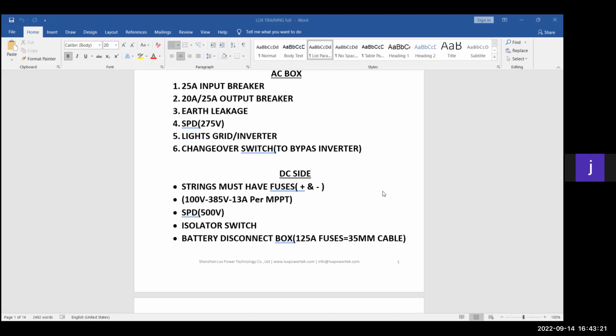So the inverter is more than comfortable to give you your 5 kilowatts worth of power from the sun if you install the panels. Now, on the panel side, we have a lot of questions on your 540 watt panels. You see a lot of them are just below 13 amps or just higher than 13 amps, like 13.1 around there. So on 540s to 545s, they are still safe to use on the system. You won't get your 13 to 13.1 amps out of your panels, even on a cold day for that short time. My MPPTs are designed to handle slightly higher amps, so you will be more than safe to use 540s.